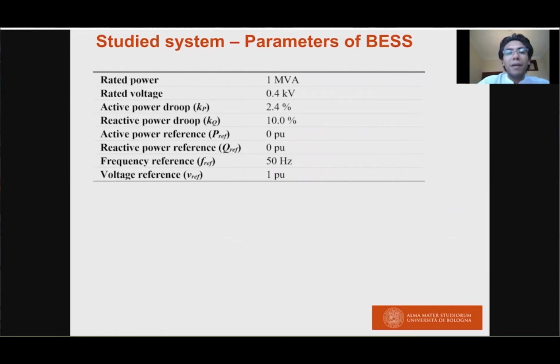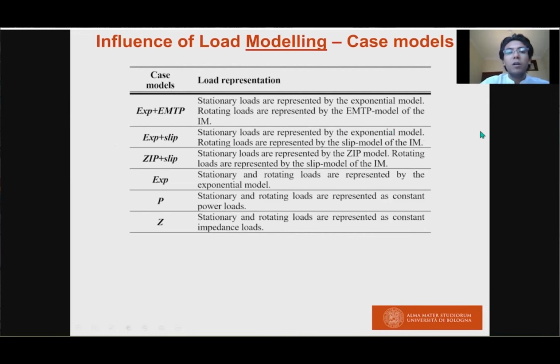We consider two 1 megavolt ampere storage systems in which the active power droop is considered to be equal to 2.4% and the reactive power droop is 10%. So we can start describing the first analysis, which is the assessment of the influence of the load modeling. 6 cases were considered. In each case, stationary and rotating loads are modeled in a specific way. For example, in the first case, rotating loads are represented by the EMTP model and stationary loads are represented by the exponential model. We retain that this model is our benchmark since it is the more detailed one.